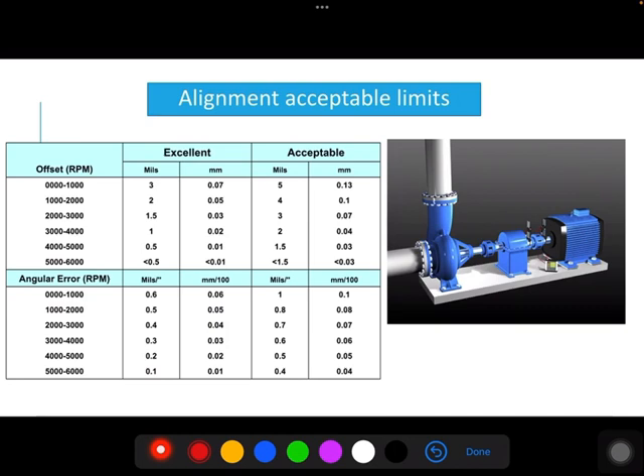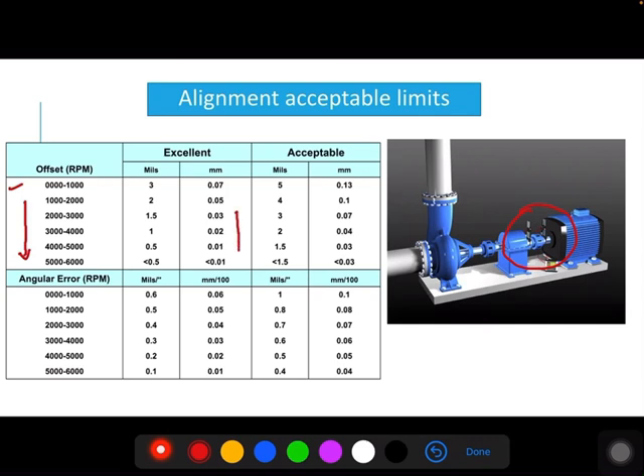To achieve precise alignment, industry generally uses a laser tool for the alignment purpose. There should be acceptable limits for any alignment condition. These acceptable limits for alignment readings mainly depend on the RPM of the machine. If the RPM of the machine increases, you should have more precise alignment between the driver and driven component.